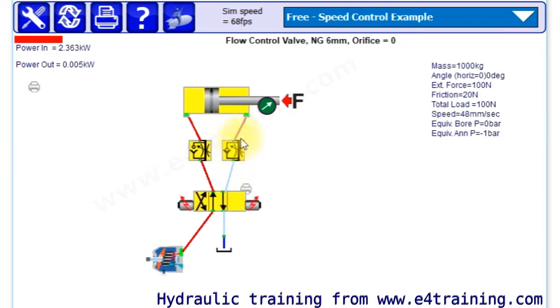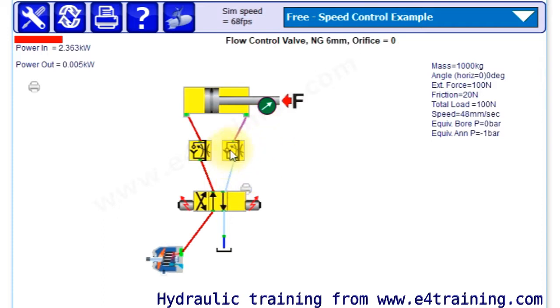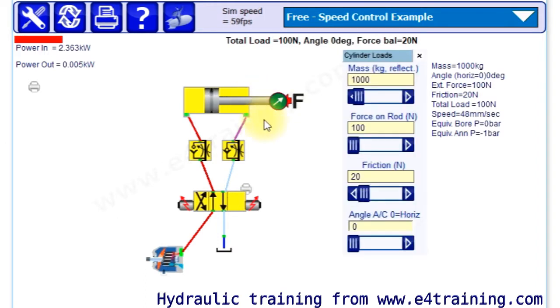Essentially that's all it is - it's a hole and you've got pressure drop across the flow control valve. That, with the size of the hole, gives you your flow rate. One of the important things I want to show is that this also depends on load because it's the pressure drop across the orifice.